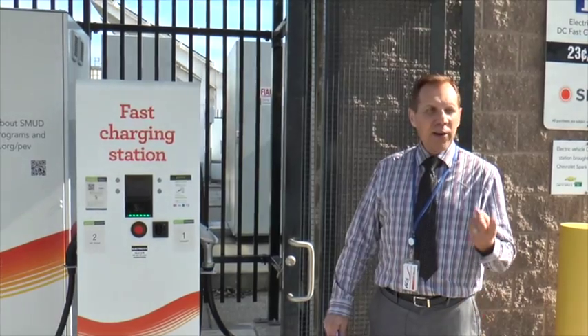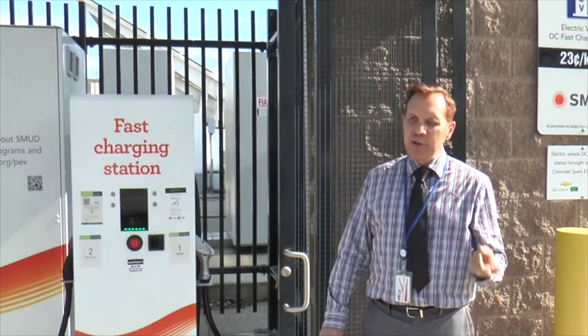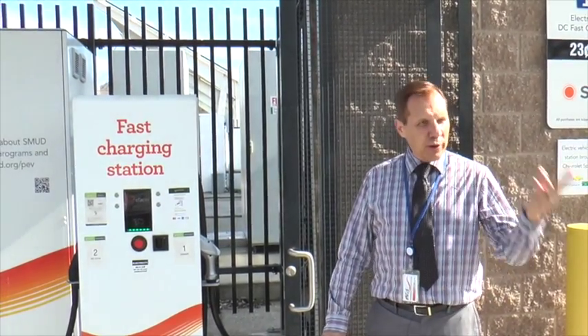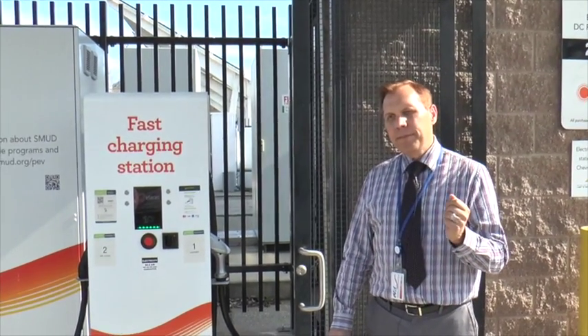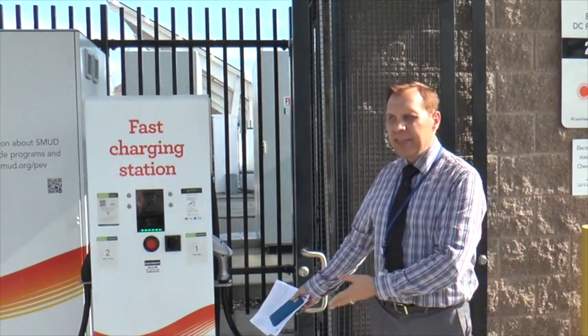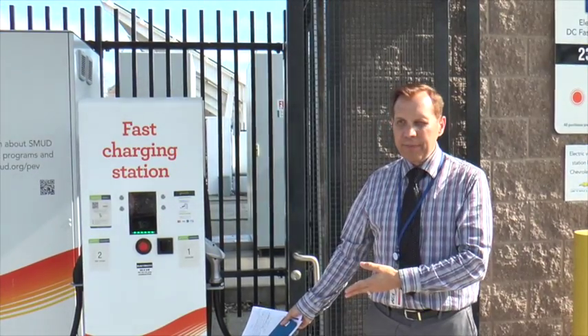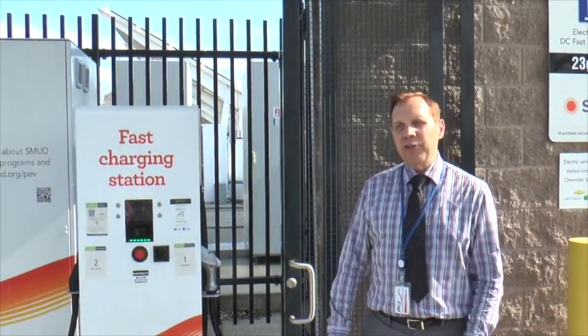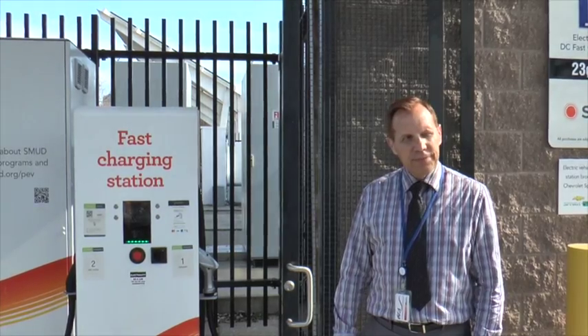Now I've got to get the new service connection, and that's $270 per linear foot for trenching, conduit, and wiring. Because it's 480, you need industrial grade switchgear, which was $60,000 for all the switchgear and the meter mains.